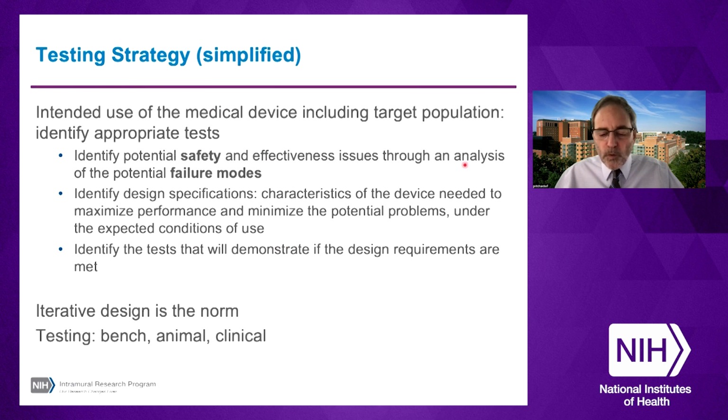You need to think through what can go wrong with my device. Can it break inside the patient? What if the pieces don't come apart? What if something gets stuck in there? What if whatever? Identify everything that can go wrong. And then during your development, you'll design your device to mitigate those failure modes and to address them.